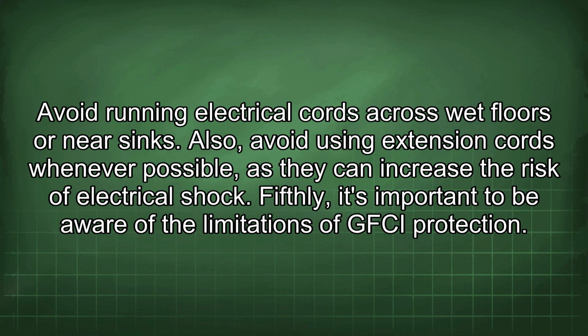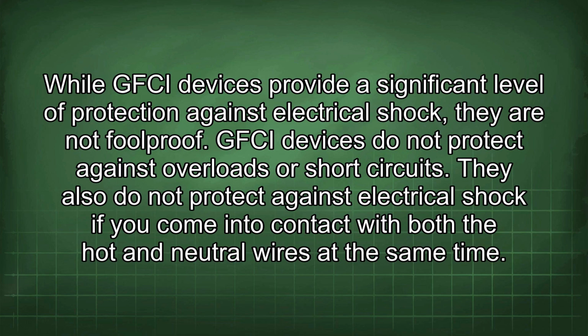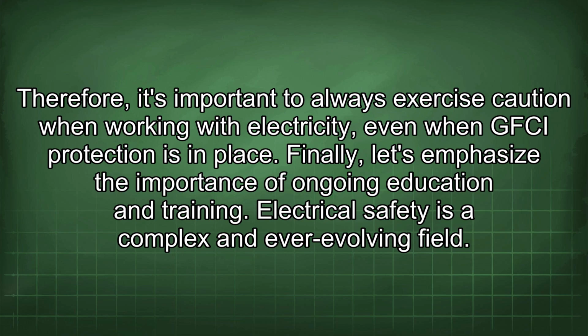Fifthly, it's important to be aware of the limitations of GFCI protection. While GFCI devices provide a significant level of protection against electrical shock, they are not foolproof. GFCI devices do not protect against overloads or short circuits. They also do not protect against electrical shock if you come into contact with both the hot and neutral wires at the same time.